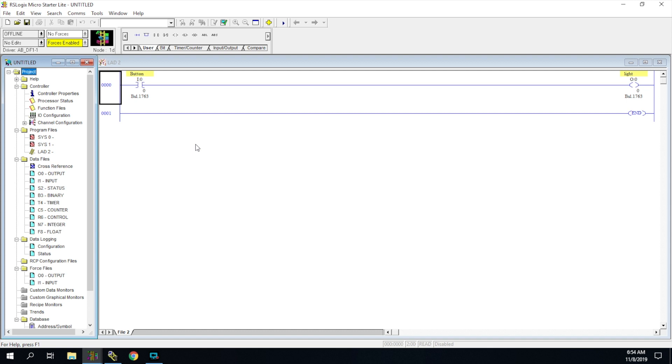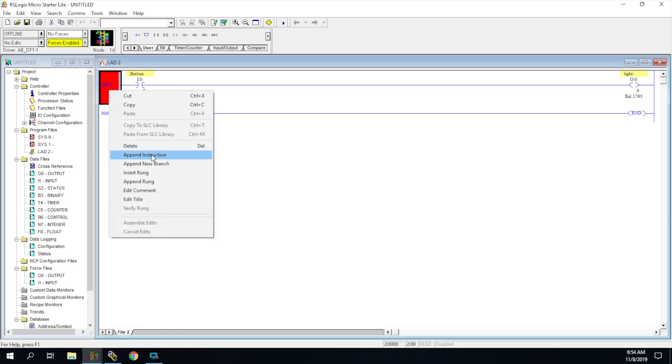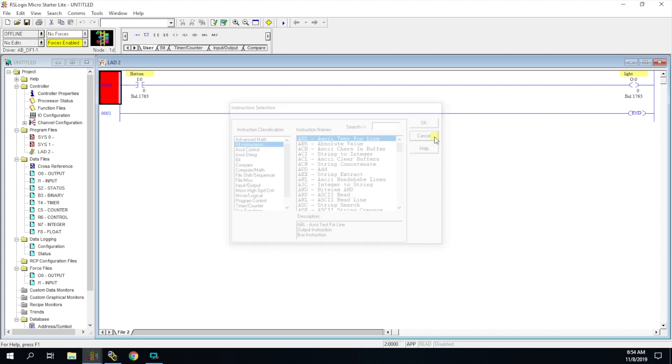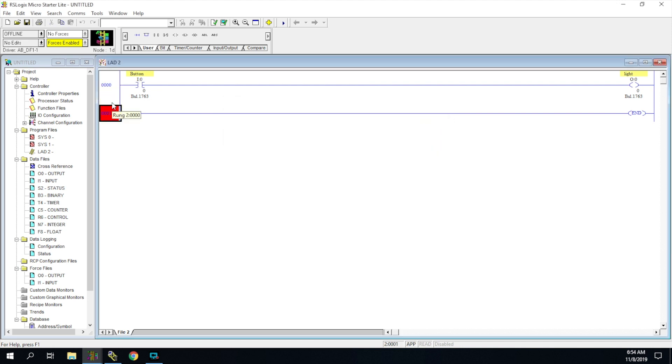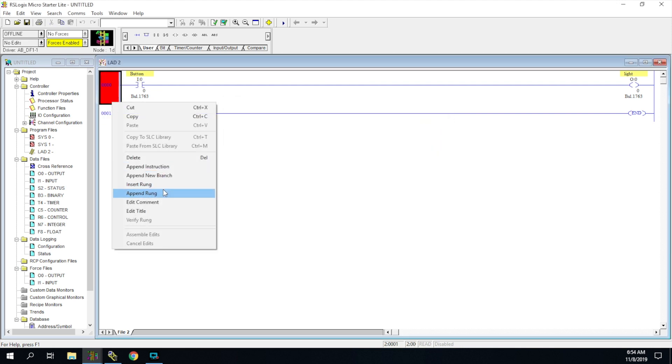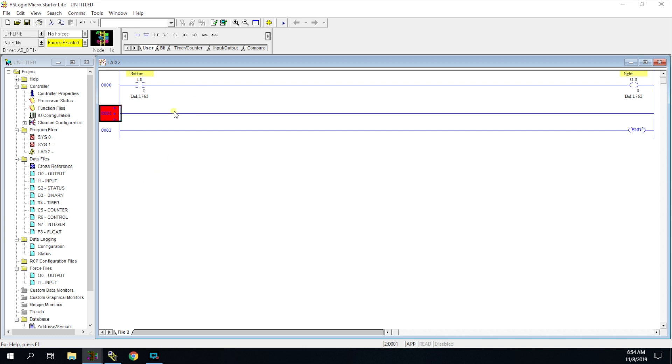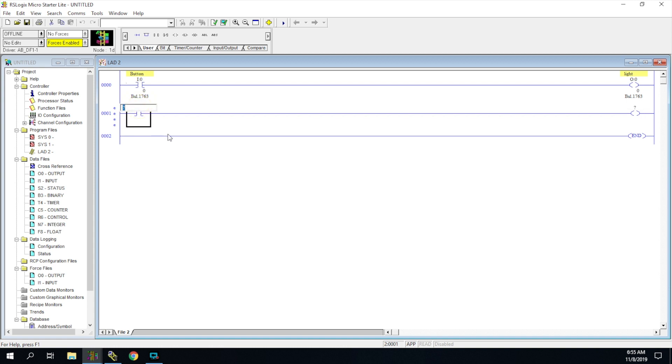Let's go offline here. We're going to continue working on this one. Now for you guys' lab, we are going to have four different buttons and we're going to have four different outputs. I showed you guys how to append a rung. There's going to be multiple rungs in this lab. So we could just come down here and I can grab another instruction and I can grab another output. This one might be the green light up here and this one might be the red light. And this one might be the limit switch that's hooked to a different input. So when I'm doing the different inputs, remember it's going to be I colon zero slash something. So if I was going to code it to a different button, I think the green button is on terminal three. So I'm going to put a three in here and I'm going to hit enter, and this is going to be green button.